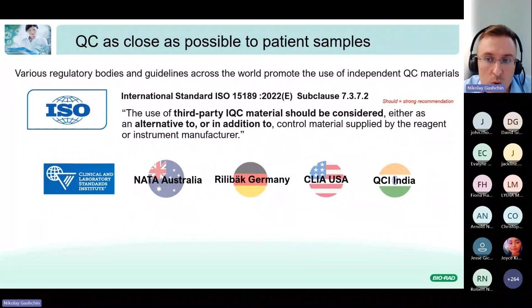I also want to highlight the long-term quality control monitoring statement, which is mentioned in ISO. It says that the procedure should also allow the detection of either lot-to-lot reagent or calibration variation, or both. To fulfill this requirement, we need a control material with quite a long shelf life, like it's shown here on this chart. So we have this independent control with a shelf life of, for example, 3 years.